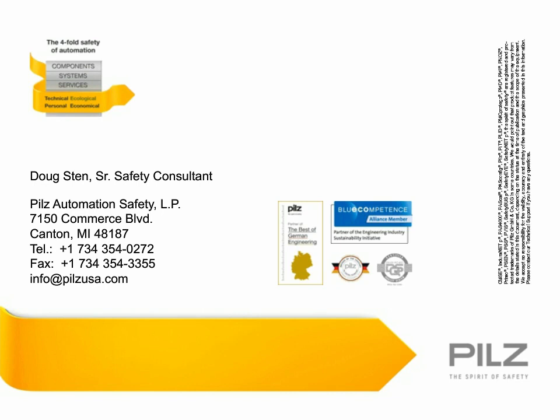What is your recommendation to protect robots? Well, robots, there is a robotic standard. It tells you what you need for what you're using it for. If there's a possibility of the product being let loose of the end of the robot, you need to have physical guarding. Your control reliability has to be at least a category 3, and if you're in Europe, you're talking about a performance level rating of at least a D, self-checking, monitoring in that perspective.